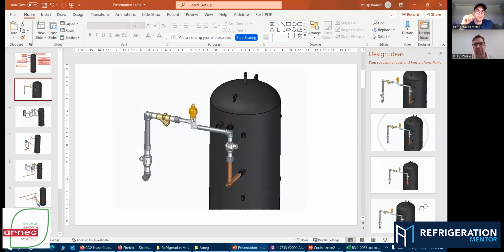Yeah, and remember, I talked to a lot of technicians who were installing some of the first systems about 10 years ago, and they said it was like night and day to the way they do it now, because they weren't as cautious about it. You know what I mean? Because they were used to doing supermarket work where you get away with a lot of stuff. With CO2, you don't get away with as much, especially with dirt in the system. They were losing high pressure valves or flash gas bypass valves, getting dirt stuck in them and causing damage, and then the system's down. So that's real cool that you add a strainer before that valve. That's so key. Awesome. Absolutely.